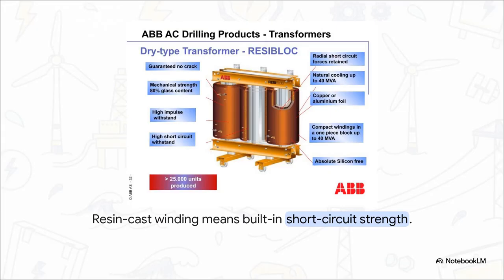And that 80% glass content translates directly into something absolutely crucial: exceptional short-circuit withstand capability. See, if a massive fault current surges through the winding, electromagnetic forces violently try to tear those coils apart. An unreinforced, loosely wound coil? It would instantly deform and fail. But because the resin has already locked the RESIBLOC's geometry into a solid mass, the winding physically can't deform. It holds its shape perfectly and just survives the surge.